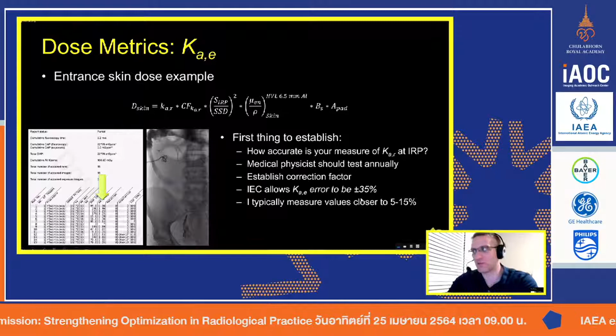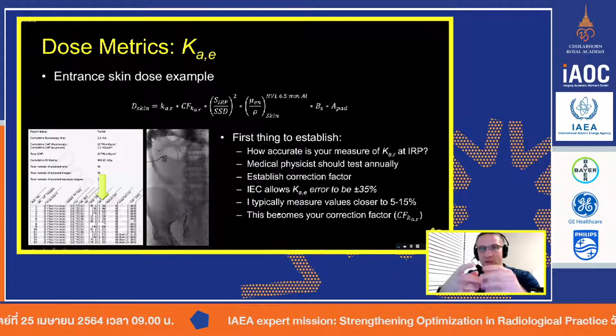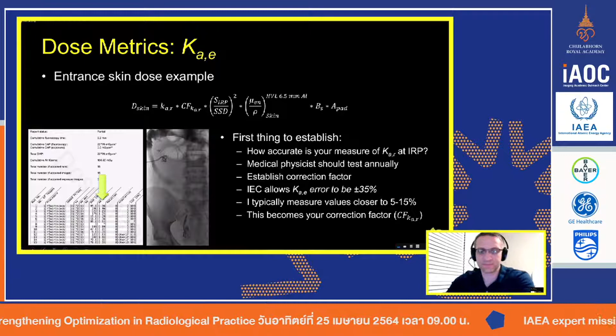I typically, when I make my measurements, see my systems are usually 5 to 15%. So the reality is, even though they're allowed to go to 35%, most of these manufacturers are doing their best to do better than that. So you go in, you make your measurements with your ion chamber and your KAP meter, DAP meter, whatever you've got, and then you compare it to what's on the screen, you do some math, and you can know what your correction factor should be. All right, so now that we can scale our air kerma value, let's look at the next point, the distancing.